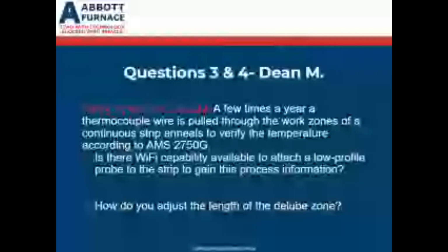If you would put that thermocouple in the hole closest to that zone, that's going to lengthen it, whereas if you would put it in the 3rd hole back, you can change the length actually by like 6 inches just by changing the location of your thermocouple, as well as like either your 2nd or 3rd zone. You would put that control thermocouple towards the rear of that zone. That would give you the maximum distance that your delube zones would be able to effectively work at, without having to, again, add a zone 0 or QDP or anything like that.